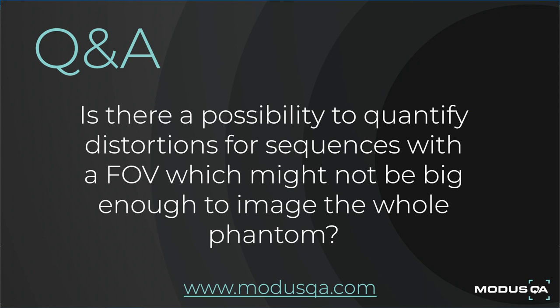Is there a possibility to quantify distortions for sequences with a field of view which might not be big enough to image the whole phantom? Fundamentally, the harmonic analysis method requires the acquisition of data around the entire volume, so currently that is not supported. But in theory, there are 2D methods that could be implemented as works in progress, and we are looking at this in the future.